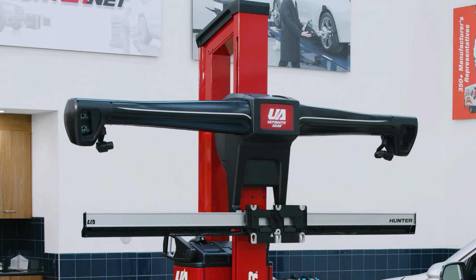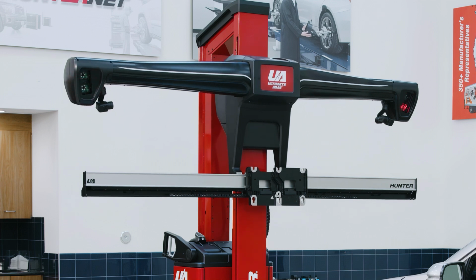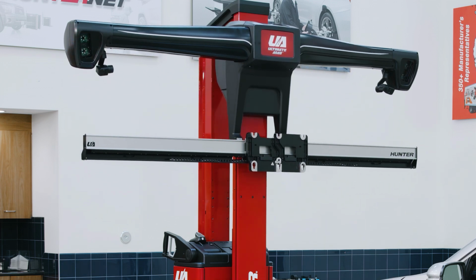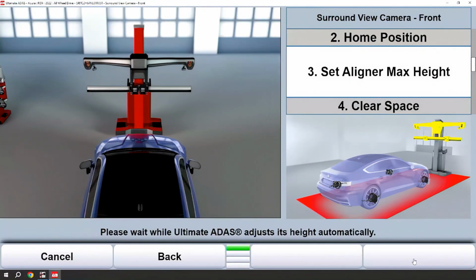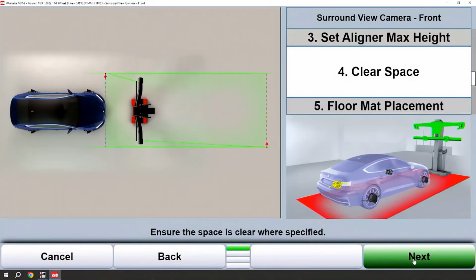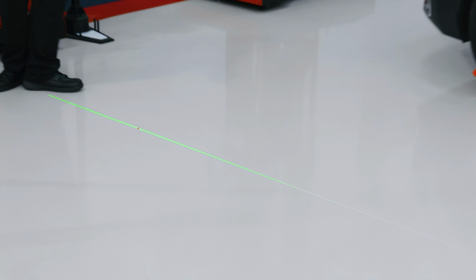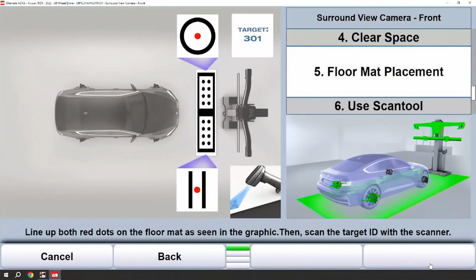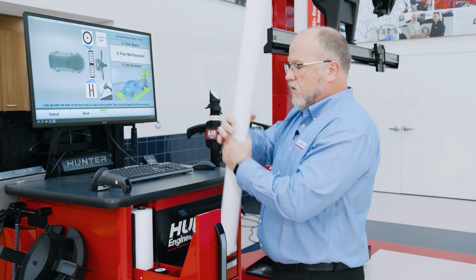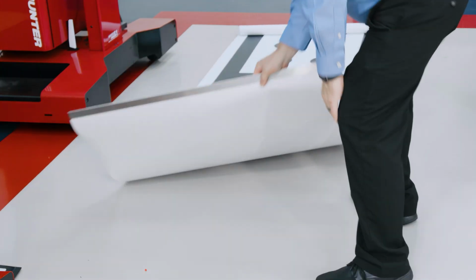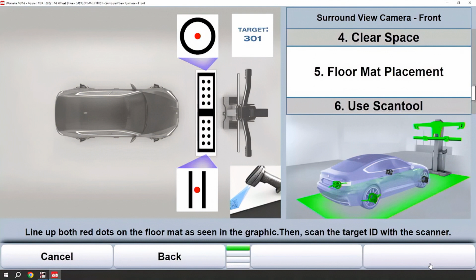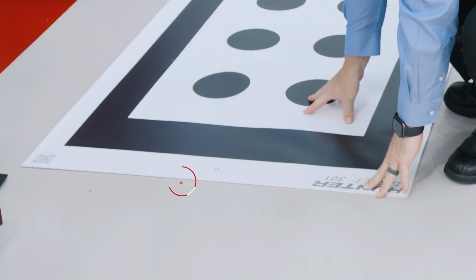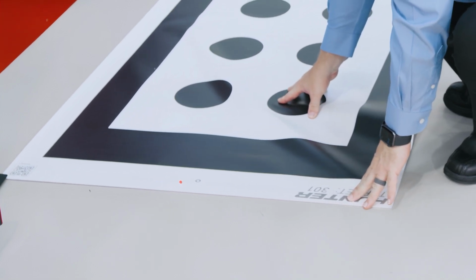We'll set those cameras and boom to the maximum height. And next we'll look at clear space to make sure that we actually have room to complete the calibration. Looks like we have ample clear space for the calibration. Let's move into mat placement. For this, we'll be using target 301. Pull that mat out of the drawer, and we'll go ahead and lay it out. For this placement, we'll have the red dot laser shining on the floor. We'll simply align that red laser with the circle on the floor mat.